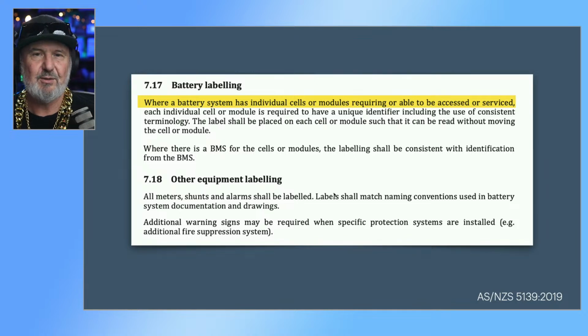Now, I did cover in a previous Toolbox Tech Talk that you don't actually need one master e-stop for a whole BESS or battery system. You might have, as I have in one of my systems here, 40 battery modules all in parallel. We don't need one big isolator for the whole 40 systems because it would be several thousand amps of switching. You can use individual switching on each battery module as long as it breaks both conductors, a positive and negative, and it's labelled. And the shutdown procedure should reference those labels. So, for instance, in my case, it will say to shut down the battery system, switch off battery modules 1 through to 40 to isolate this battery system. So, yeah, you don't actually have to have one big master switch.